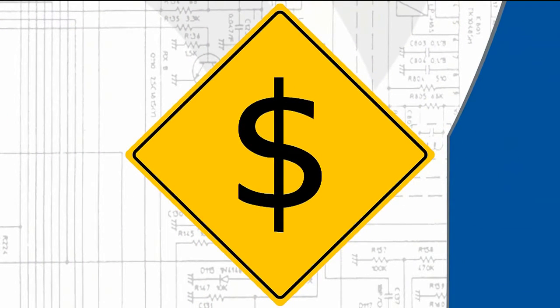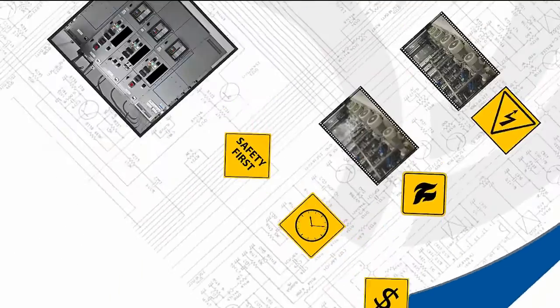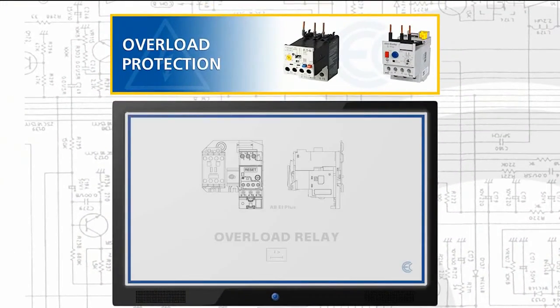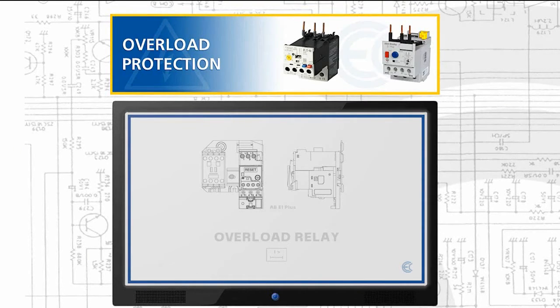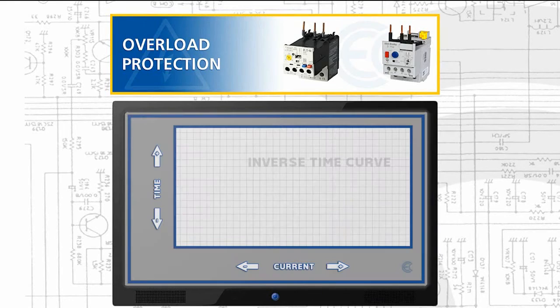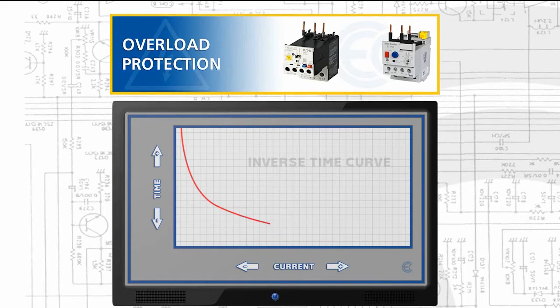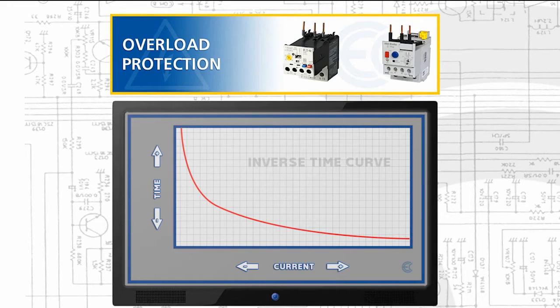Let's dive into the differences between short circuit versus overload protection. Overload protection is protection against a running overcurrent that would cause overheating. Overload protection typically operates on an inverse time curve where the tripping time becomes less as the current increases. This means an overload relay isn't going to trip on momentary or short-term overcurrent events that are normal for the piece of equipment it is protecting.